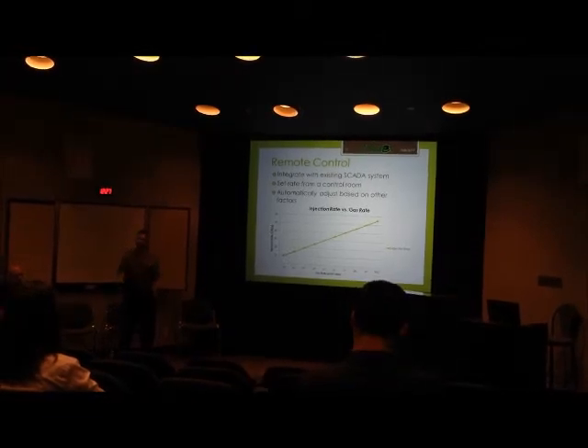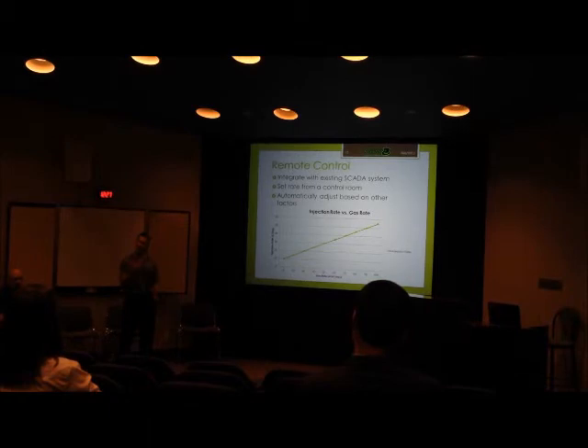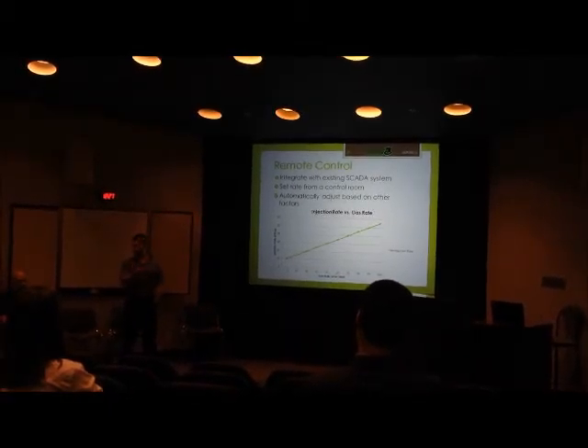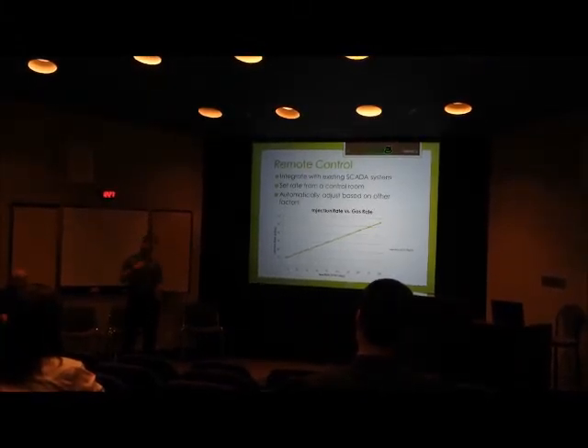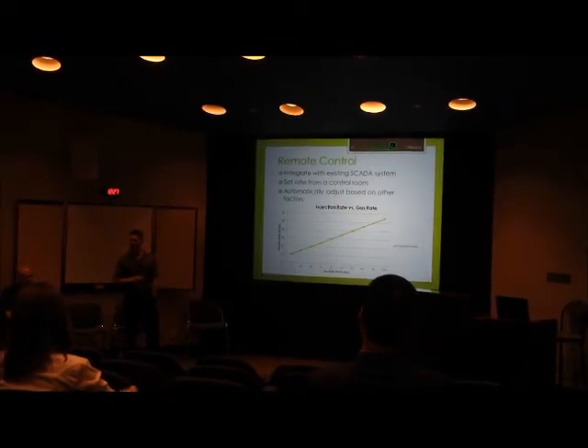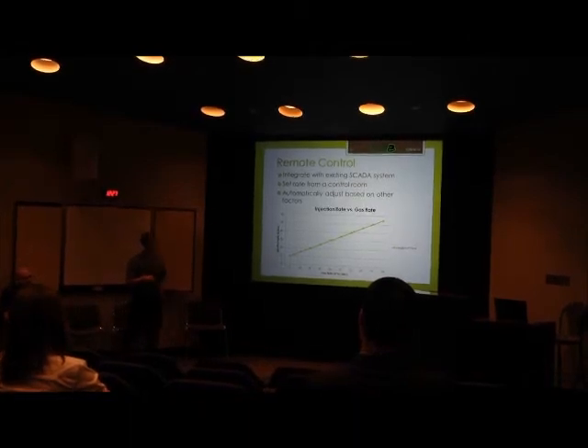Through SCADA, now the operator can just go on recycle. Hits recycle. The pump doesn't shut off, it never loses prime, it just sits there and recycles back to tank. Field gets ready to go pick up, the operator hits the choke button to open the well, he just hits run again, program automatically picks back up, you haven't wasted a liquid chemical the whole time that well's been shut in. Big advantages tied into SCADA.